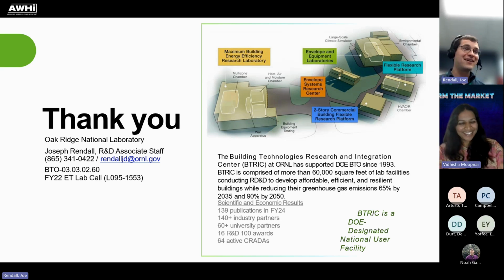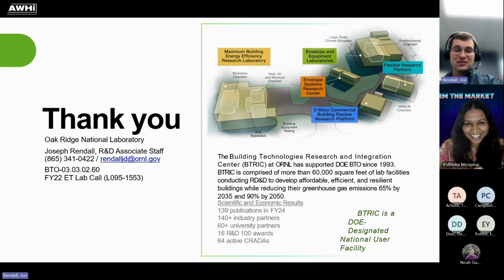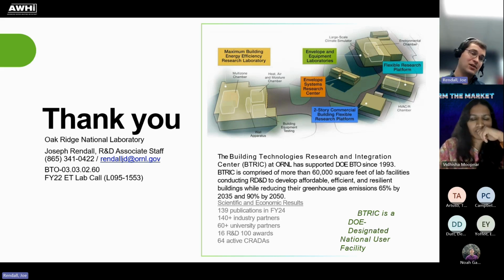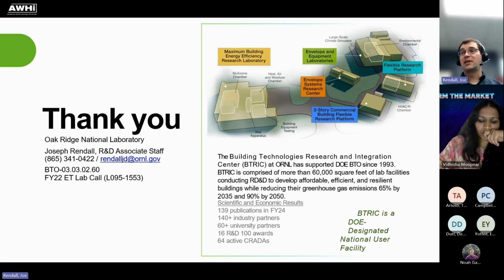In our case, what we did, and it's a little conservative, is when we were first doing our sizing, and as I'm reviewing it going forward, we were trying to replace half of the BTUs of natural gas by tripling the storage. If you go look at EcoSizer's work, you might not even have to do that. So having an additional heat pump, which is where we're at on one of our projects, when we sized it with EcoSizer we were double the size on BTUs per hour. That's one less heat pump, which reduces your costs by $40,000 to $50,000, which is really significant.